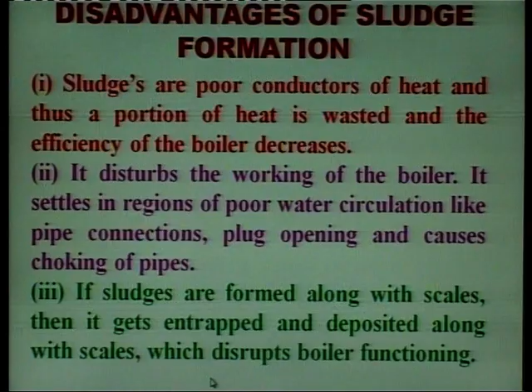Disadvantages of sludge formation. First, sludges are poor conductors of heat, and thus a portion of heat is wasted and the efficiency of the boiler decreases. Second, it disturbs the working of the boiler. It settles in the regions of poor water circulation like pipe connections and plug openings, and causes choking of pipes. Third, if sludges are formed along with scales, then they get entrapped and deposited along with scales, which disturbs the functioning of the boiler.